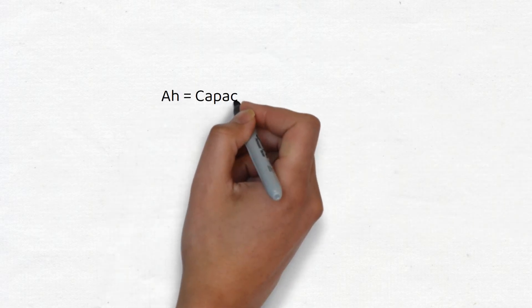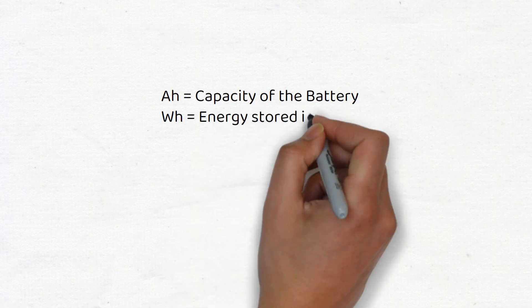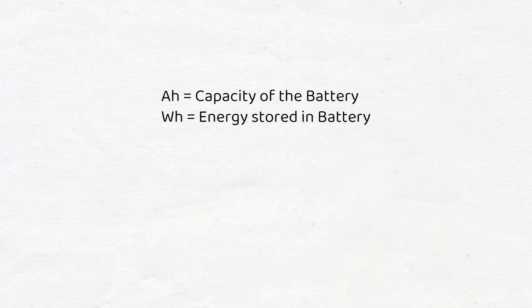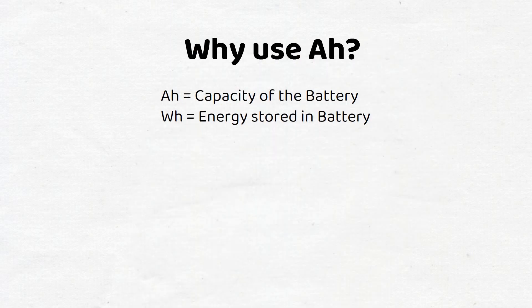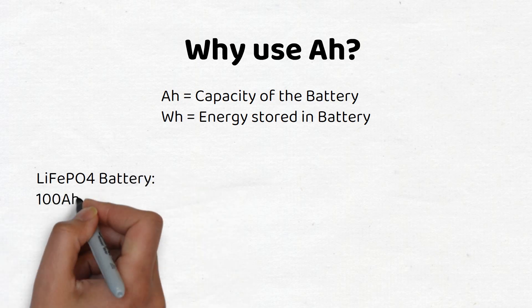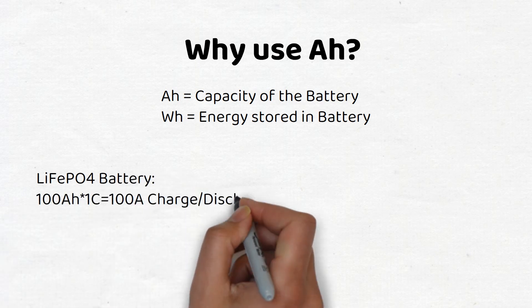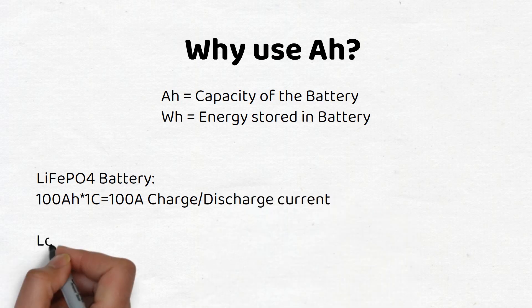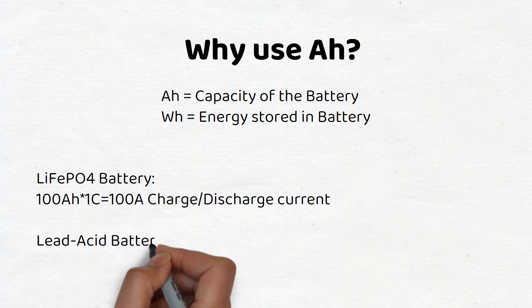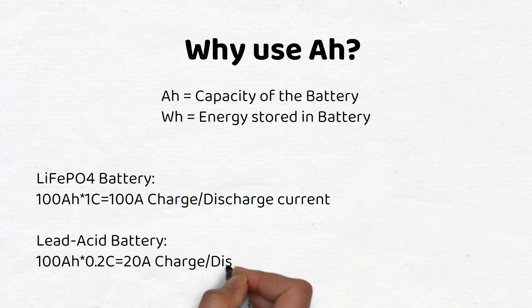In essence, amp hours gives insight into a battery's capacity, while watt hours reveal the total energy it can store. Amp hours should be used to calculate the charge and discharge rate of a battery, also called C-rate. The C-rate of a lithium battery is 1C, while it is 0.2C for a lead acid battery.